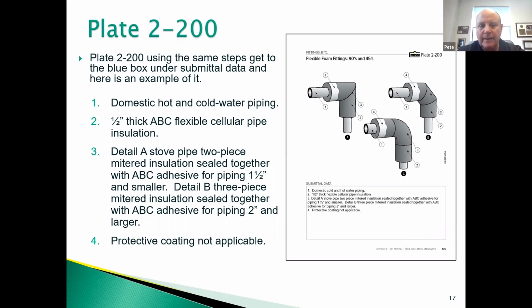Number 3, we're going to select detail A, stovepipe 2-piece mitered insulation sealed together with ABC adhesive for piping 1.5 inches and smaller. Then we're going to state detail B, 3-piece mitered insulation sealed together with ABC adhesive for piping 2 inch and larger.